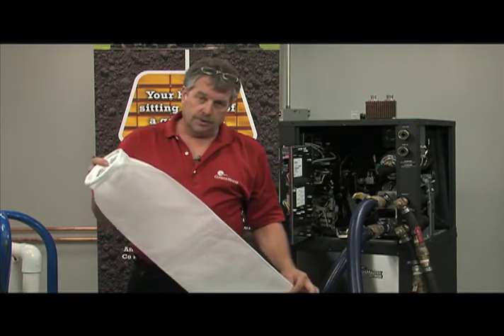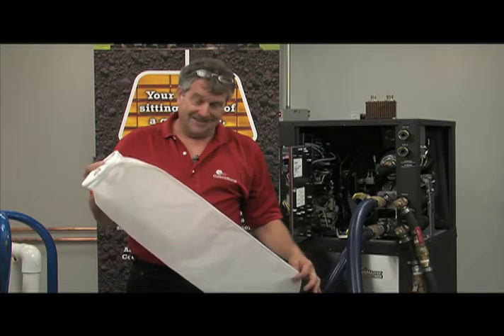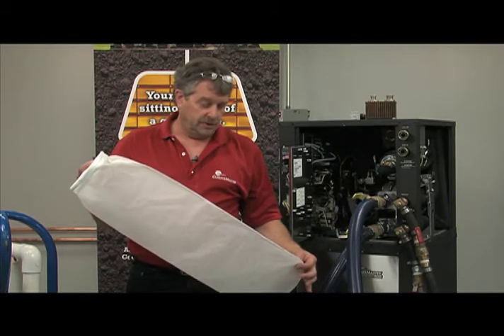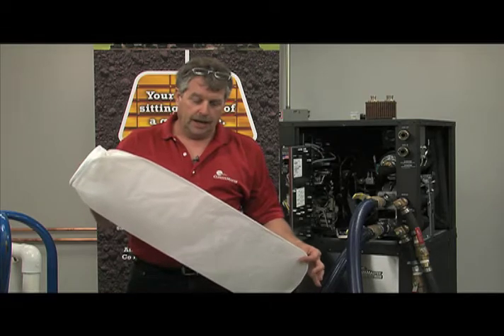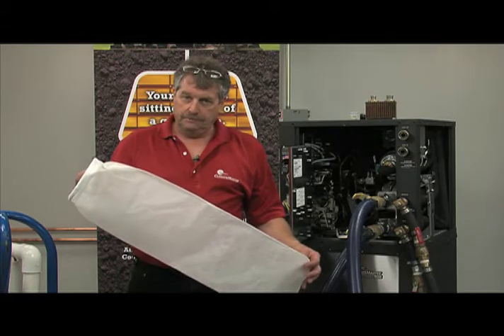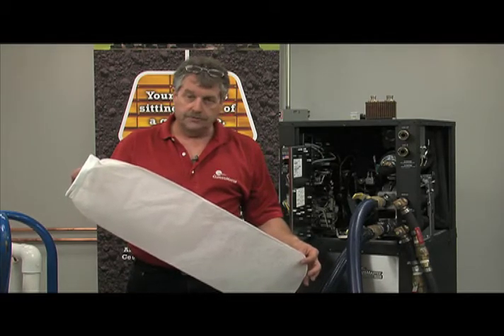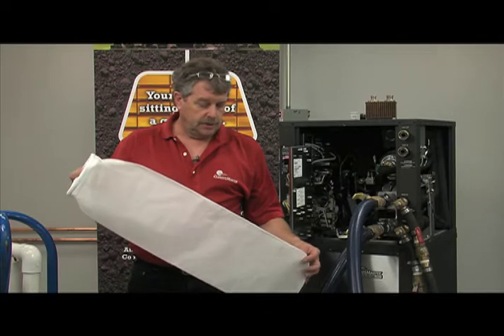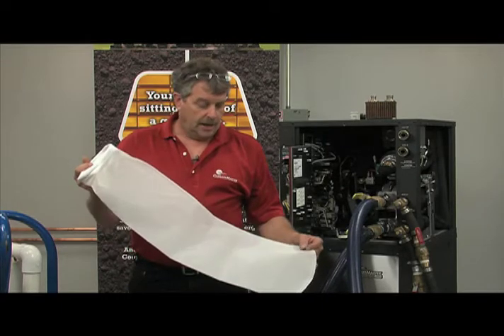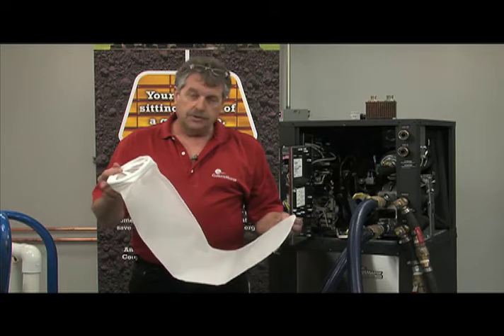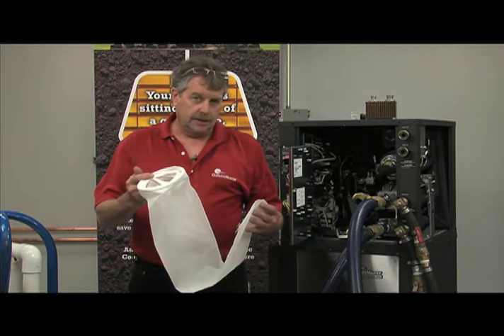One of the critical components, especially on the Trilogy, but as well on the vFlow Connect, because we do have some other components I'll get to in a moment, you want to properly filter that loop fluid. This happens to be a 100 mesh filter bag. It comes into the flush cart that we provide. This again is a 100 mesh. You don't need quite that robust. It could be an 80, that'd be just fine.